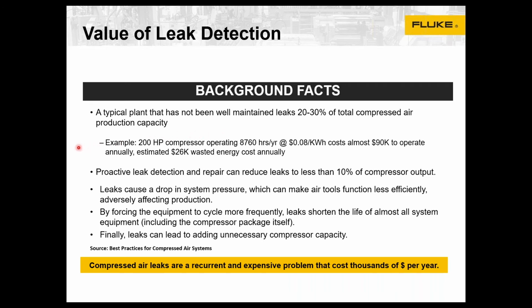So to make this a little more real, let's say you have 200 horsepower total of compressors. They're operating nonstop year-round. Your base rate to run those things electrically is 8 cents a kilowatt hour. It's going to cost you around $90,000 to run those, and you're wasting about 26K of energy annually, based on the Department of Energy figures. So it pays to try and minimize that. Also, the DOE has shown that by being proactive, implementing a program, you can get that down to less than 10%. So you can save maybe up to about 20% of those annual energy costs every year.